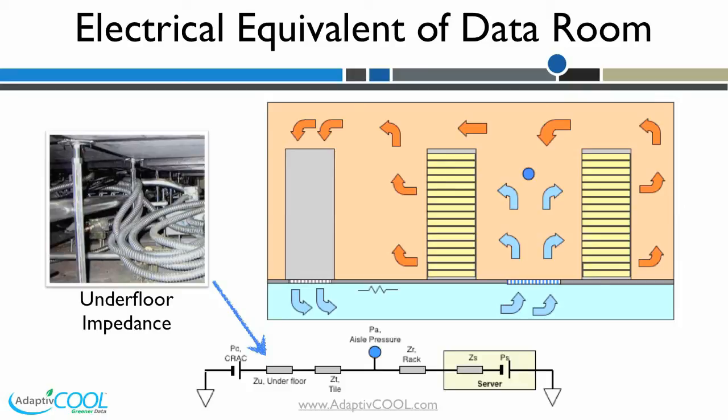The underfloor impedance between CRAC and the rack determines the amount of air flow that is discharged from the floor at the rack. Therefore, the underfloor impedance plays a significant role in air flow availability and rack temperatures at different locations in the data center.